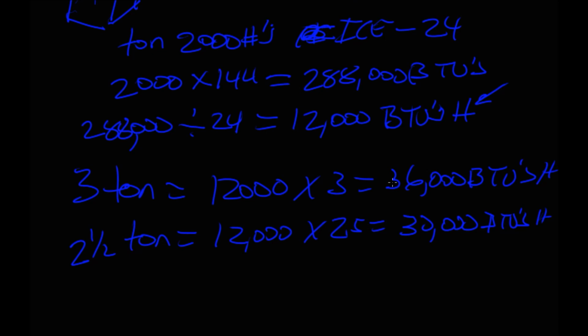So if we're talking this lingo to you in the future, and you hear a guy saying it's a 3-ton or 2.5 ton, you'll know that it doesn't weigh 3 tons or 6,000 pounds, that it's actually 36,000 BTUs the unit should be producing.